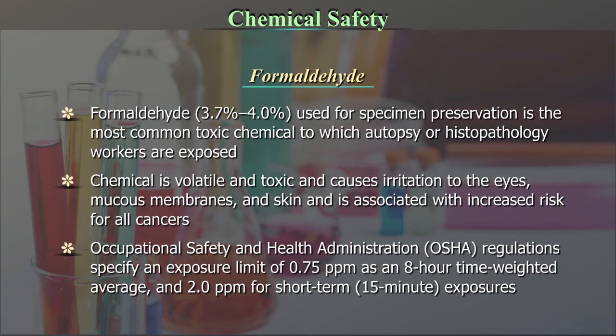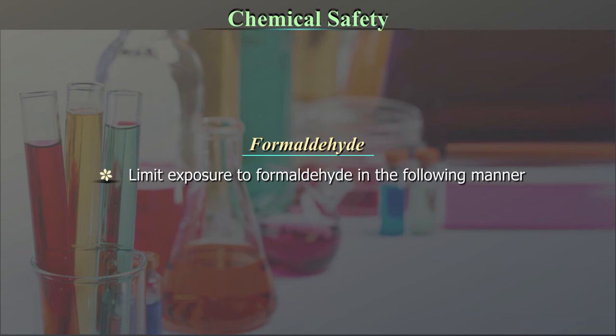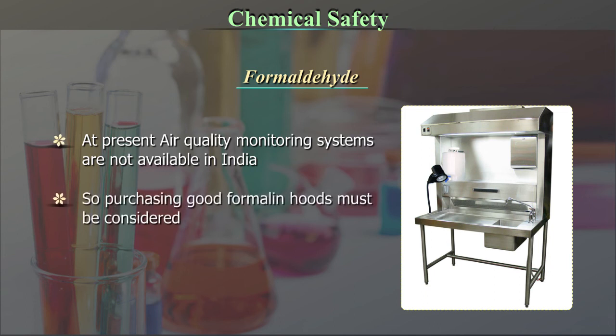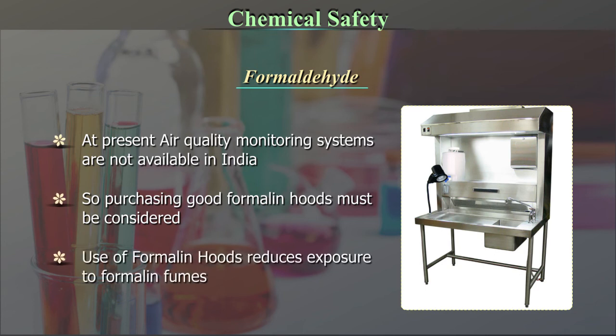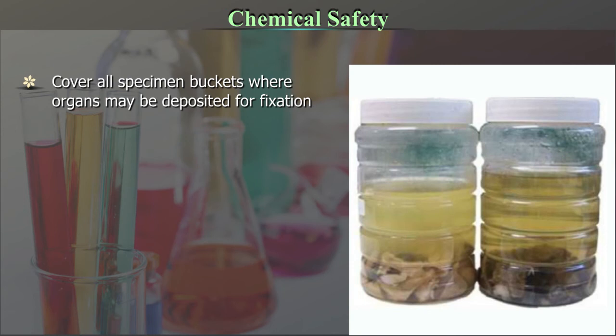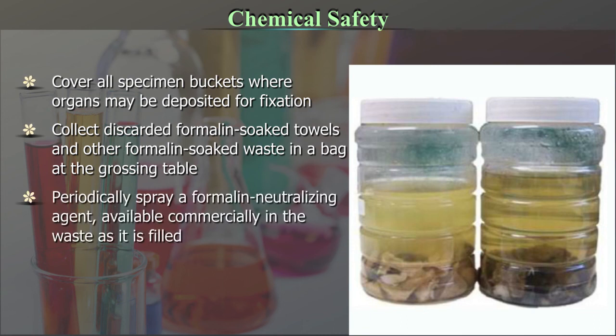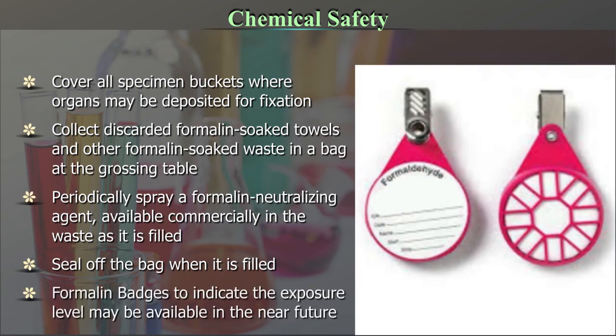Formaldehyde: Occupational Safety and Health Administration regulations specify an exposure limit of 0.75 parts per million as an 8-hour time-weighted average, and 2 parts per million for short-term (15-minute) exposures. To limit exposure to formaldehyde: at present, air quality monitoring systems are not available in India, so purchasing good formalin hoods must be considered. The use of formalin hoods reduces exposure to formalin fumes. Cover all specimen buckets where organs may be deposited for fixation. Collect discarded formalin-soaked towels and other waste in a bag at the grossing table. Periodically spray a formalin-neutralizing agent in the waste as it is filled, then seal the bag when full. Formalin badges to indicate exposure level may be available in the near future.